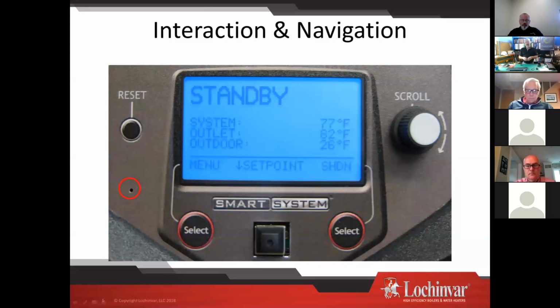Now, when you do that, the boiler is going to fire to 100%. Tap it again, your boiler will drop to its minimum firing rate. If I have this blue screen with the gray bezel, that's 20%. That's its minimum firing rate. If I have the red bezel, like I showed you earlier, that's 10%. Once the boiler is in that service mode, we go back to that knob and we can actually adjust the firing rate with the knob.